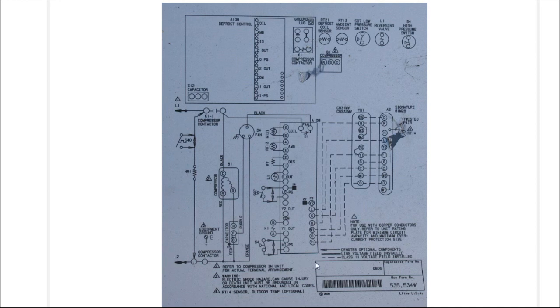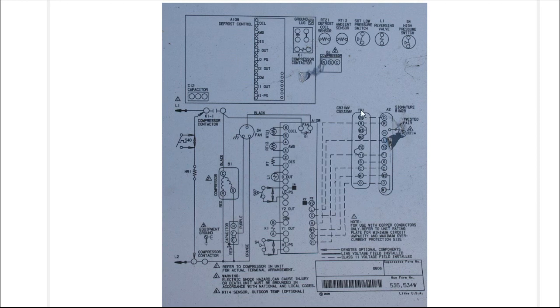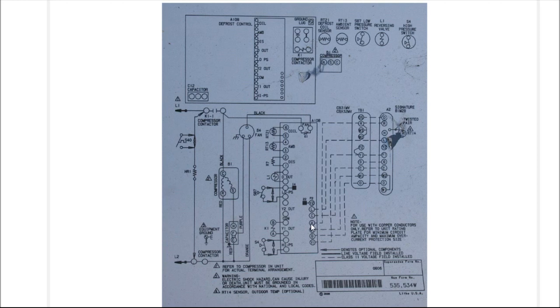This just goes out to your home and connects up to the disconnect. The dotted lines designate class 2 voltage field installed. Class 2 voltage is your low 24-volt control voltage wiring that the installers use to connect the test board one on the air handler, the CBX 32, which could be in the garage, could be in the attic, could be in the basement. So this denotes the low voltage control wiring that goes from the air handler into the condensing unit on the outside of your home.